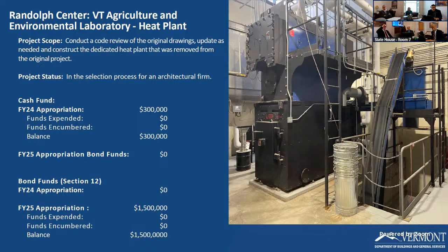And because of our issues with the steam coming into the building, we were looking to build that heat plant now. The issue with the college is that during the design process, there was not good communication between the design team and the college. The autoclaves in the building require 60 pounds, 60 PSI. The college has a max of maybe a 50 to 60 range. The college can only provide us at best 48 PSI.